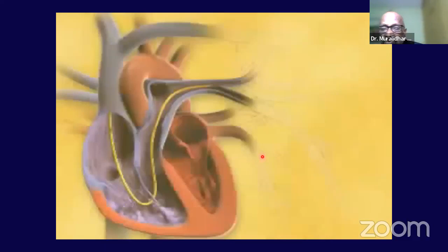And the other method is continuous cardiac output, where there's a thermal filament, which is heated to 42 degrees in a pseudo-random fashion. And the amount of heat generated here is measured at this point by the use of a thermistor. And then here you're heating the blood to about 42 degrees. Pulses of heat waves are generated and given to the blood here. And the change in the temperature is sensed here by looking at the temperature change.